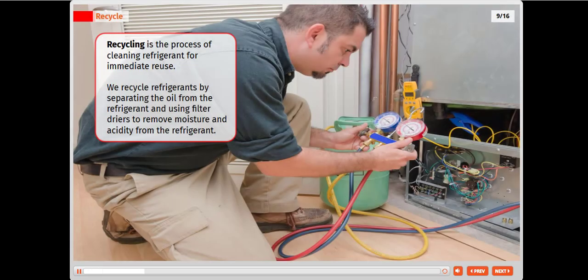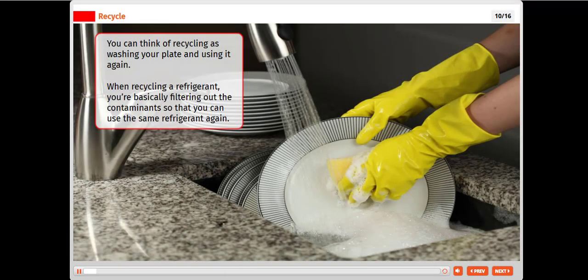Recycling is the process of cleaning refrigerant for immediate reuse. We recycle refrigerants by separating the oil from the refrigerant and using filter dryers to remove moisture and acidity from the refrigerant. You can think of recycling as washing your plate and using it again. When recycling a refrigerant, you're basically filtering out the contaminants so that you can use the same refrigerant again.